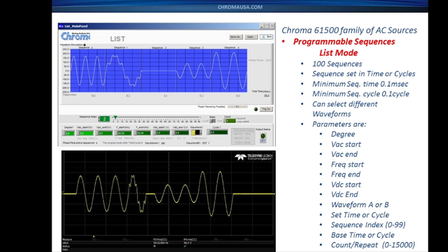You can program up to 100 sequences. Each sequence can have a different time, or you can also change it to a different cycle count. The minimum sequence time is 100 microseconds or 0.1 millisecond. The minimum cycle count is 0.1 cycle. You can do different waveforms and program in different parameters.